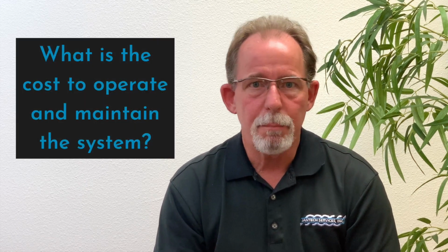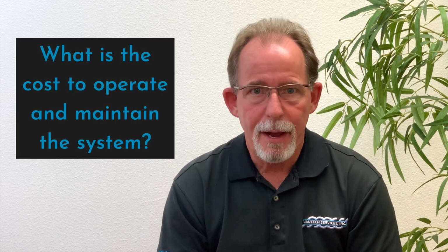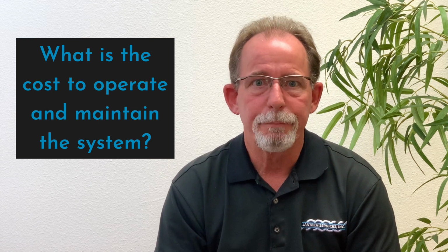The second question would be: what's the cost to operate and maintain that system? Meaning power usage, maintenance cost, etc. The only criteria outside of a high operating cost - meaning it's just burning way too much utility power - or the maintenance cost has gotten way out of hand, would be if, hypothetically, you had a larger system, say a 100 kVA system, and your load's down to 20 kVA now, and you don't anticipate that load growing anytime in the future. And the third question is: are parts available for the system?